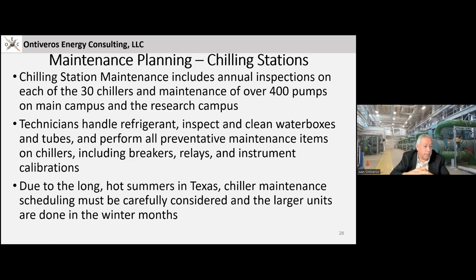So our technicians handle refrigerant. They inspect and clean the water boxes and the tubes, all the preventive maintenance on the chillers, including breakers, relays, and instrument calibration. Calibration, I didn't touch on that before, but it's very, very important. You can have all this instrumentation, but if it's not calibrated and you're trying to use that to optimize, well, bad data in, bad data out. So calibration is very, very important. And also because it's so hot, chiller maintenance was scheduled for the winter months. And the same thing with turbine maintenance. We do different shifts, bring guys early, leave early. It also had a good benefit for them, but also was realistic because we didn't want someone to get heat prostration, for example.